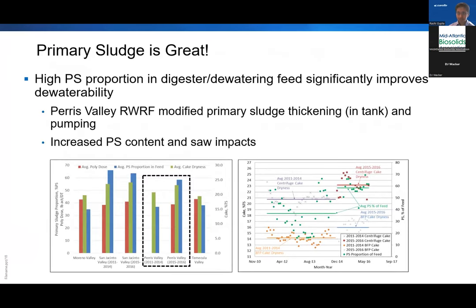So first, they convinced themselves that primary sludge is really, truly great for dewatering and digestion. So a high primary sludge proportion significantly improves dewaterability. And the Perris Valley plant, all of these facilities, they thicken in tank. So they thicken inside their primary clarifiers. The Perris Valley facility was able to modify their pumping so that they still thickened in tank, but they didn't leave the material in there long enough for it to start fermenting or anything. They pulled it out more quickly and they were able to get that load out of the primaries and into the digestion and dewatering processes.